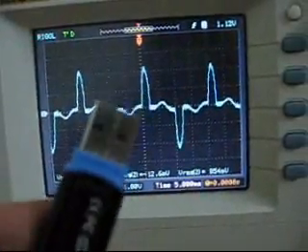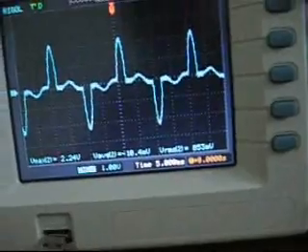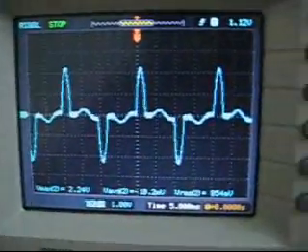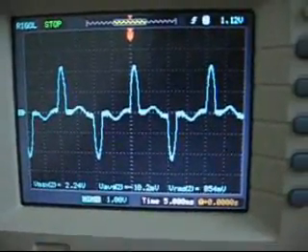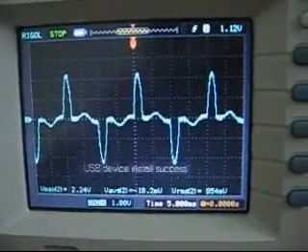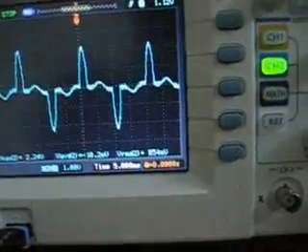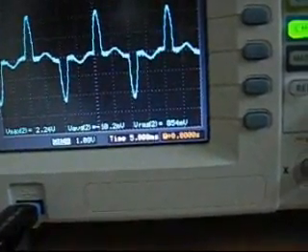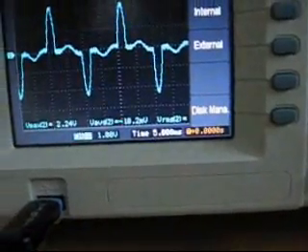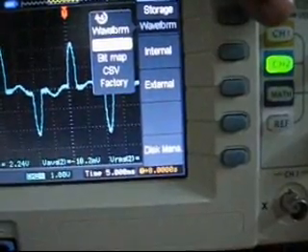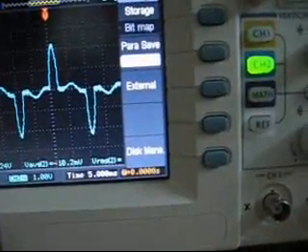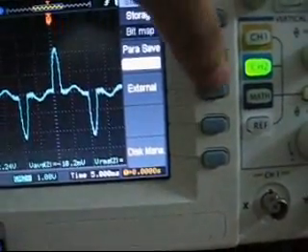I have this USB drive. Let me connect it and see how it stores data. First, let me freeze the waveform — I've stopped the waveform so it doesn't move. I've connected the USB drive, and now I go to storage, select waveform bitmap, and choose external.